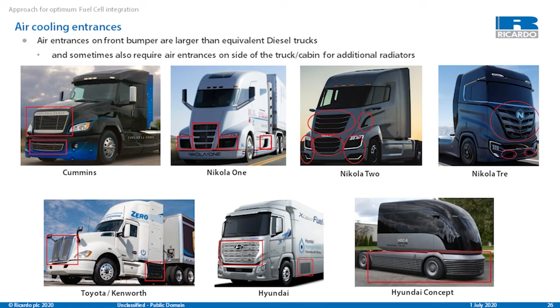One tricky part about thermal management to consider is the sizing of the radiators. Looking at a project we worked on, we had approximately a 230 kilowatt fuel cell, and we did a calculation showing that we needed about 6.5 cubic meters per second of airflow to take that heat out.